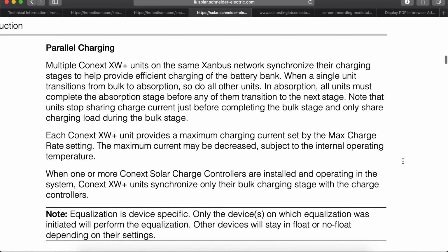Parallel charging. Multiple Conext XW Plus inverter units on the same Xanbus network synchronize their charging stages to help provide efficient charging of the battery bank. This would be from an AC source like grid or generator. When a single unit transitions from bulk to absorption battery charge stage, so do all other units. In absorption, all the units must complete the absorption stage before any of them transition to the next stage.